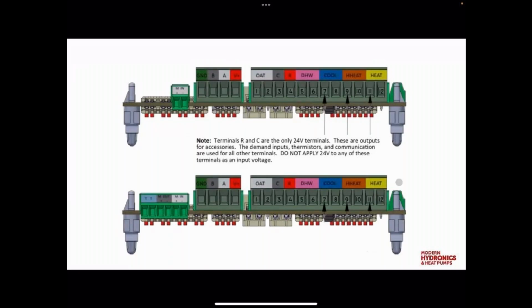And then when we get down here to the dual fuel board, like I said, all these ports starting on the right, moving all the way over, are exactly the same. The calls are the same, dry contacts, but you can see over here that this green connector is different. We still have the modulating in, so we can still receive that 0 to 10 signal from an external controller. However, right next to it now we have a modulating out port, and then the last two on the far left are TT, and that's just a common dry contact right there.